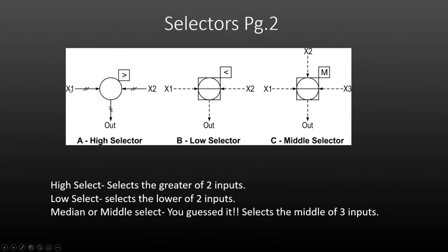So if I had 50% coming in on X1 and 60% coming in on X2, the signal going out would be the greater of the two, or 60%. The second type, image B, is a low selector and it selects the lower of the two signals. With 50% and 60% in, our output is going to be 50%.